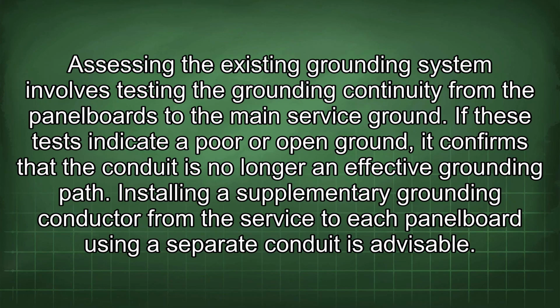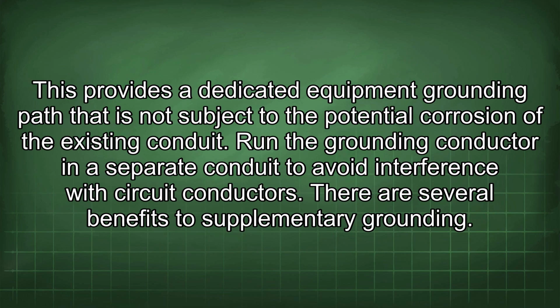Assessing the existing grounding system involves testing the grounding continuity from the panelboards to the main service ground. If these tests indicate a poor or open ground, it confirms that the conduit is no longer an effective grounding path. Installing a supplementary grounding conductor from the service to each panelboard using a separate conduit is advisable. This provides a dedicated equipment grounding path that is not subject to the potential corrosion of the existing conduit.